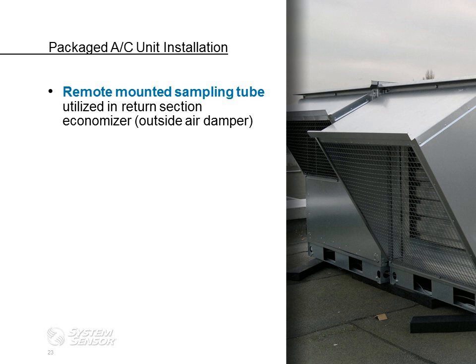You may also see remote mounted sampling tubes utilized in the return section or the economizer, which is an outside air damper of the commercial units. That's perfectly acceptable. What is required is not necessarily that the duct detector be located in a specific place, but that the air sample is drawn from a specific area. So remote sampling is acceptable and allowed.